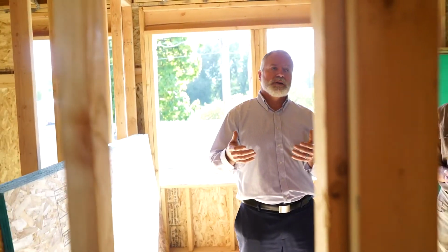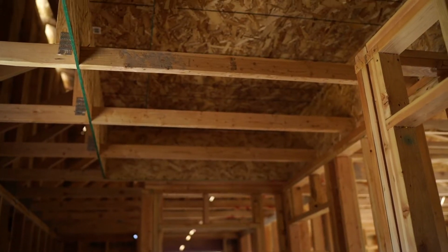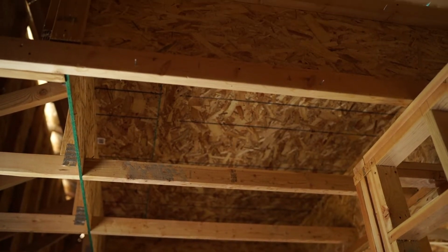A series of trusses bring your roof together. In this instance, we knew we wanted this tunnel for our HVAC system, and we only needed to change three trusses to accommodate that. By changing 3 trusses and allowing for that tunnel, our framers did on-site framing to fill in the areas you still need to insulate around the outside perimeters, and to hang sheetrock. You need that space to hang the sheetrock and to provide for the tunnel to be well insulated. So the framers lined it with OSB to create an air barrier at the top, then put in false rafters to support the drywall below.